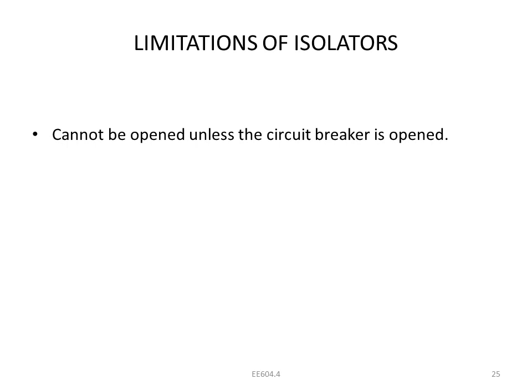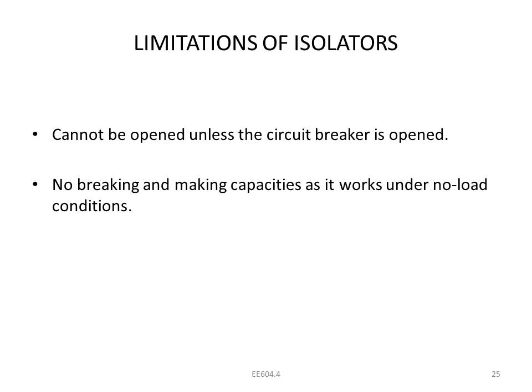Okay, if the total fault occurred on the isolator only, it should open. And when the circuit breaker is open, that is the trip circuit, only then should we open the circuit. So no breaking and making capacities; it works under no-load conditions. While operating the isolator, there should be no load conditions, first thing.